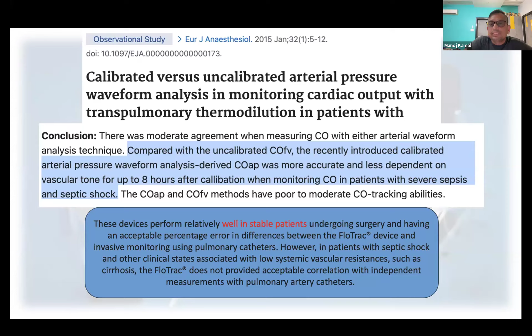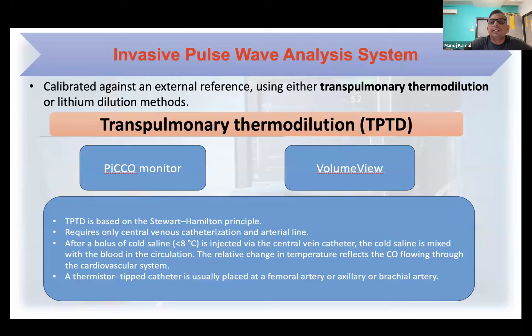Among the transpulmonary thermodilution methods, the PiCCO monitor and VolumeView monitor are most commonly used, and they require central venous catheterization and an arterial line. We inject a small bolus of cold saline via the central venous catheter, and the cold saline is mixed with the blood, and there is a relative change in temperature which is reflected through the thermistor tip catheter, which is usually placed in the femoral artery or any other great artery. So the PiCCO system is the first system which was approved in 2000 for clinical use, and it uses a specific algorithm, a combination of real-time continuous monitoring through pulse contour analysis, calibrated intermittently by the transpulmonary thermodilution method, and it analyzes the systolic part of the arterial waveform.